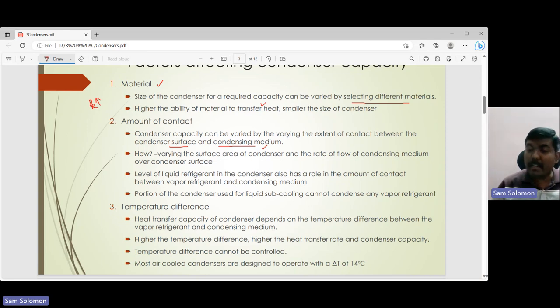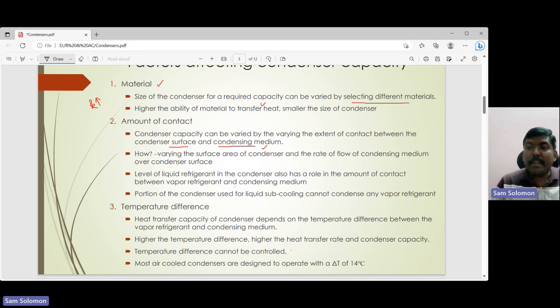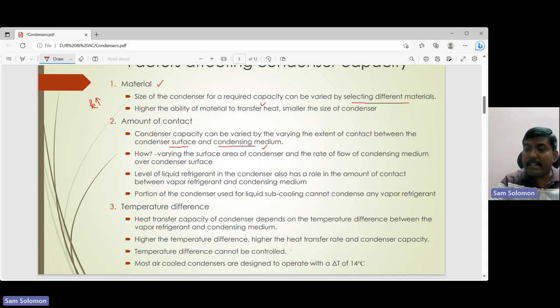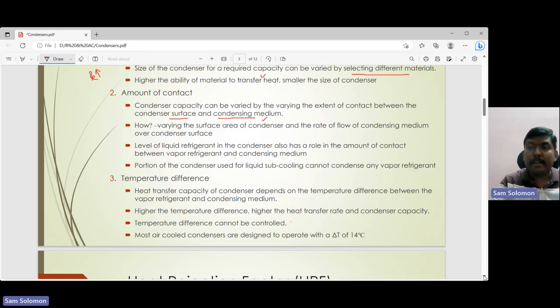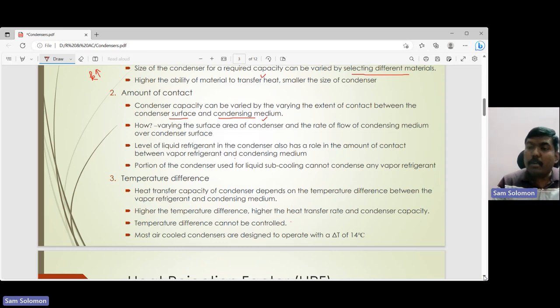The temperature difference cannot be controlled, because converting a particular vapor into liquid requires a specific temperature difference that cannot be altered. Most condensers are designed to operate with a temperature difference of around 14 degrees centigrade. So the factors affecting condenser selection are: material, temperature difference, and the amount of contact of the condensing medium with the condenser surface.